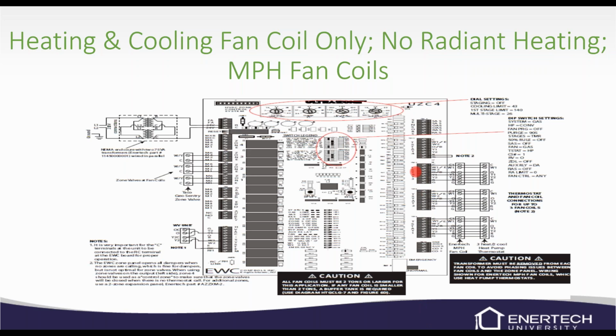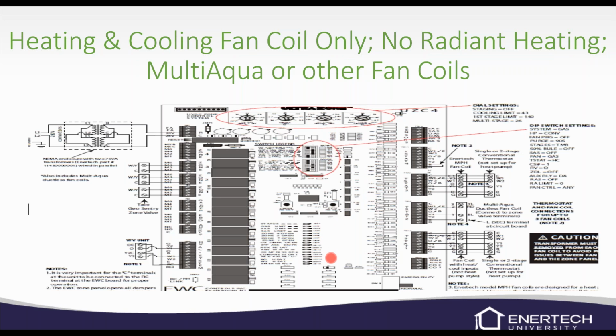Basically, thermostats on the right, and we've got our zone valves on the left, our WV input on the left, and then just some more settings up top. Same thing with no radiant when you're using multi-aqua or other types of fan coils. It's really a very similar setup. You have to be careful on some of the air handlers. They may not be set up for heat pump. They may be set up for a standard conventional system. So you may have to manipulate it a little bit, but we do list notes and things here for wiring those in.